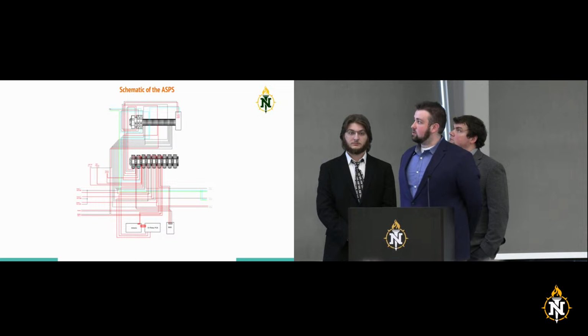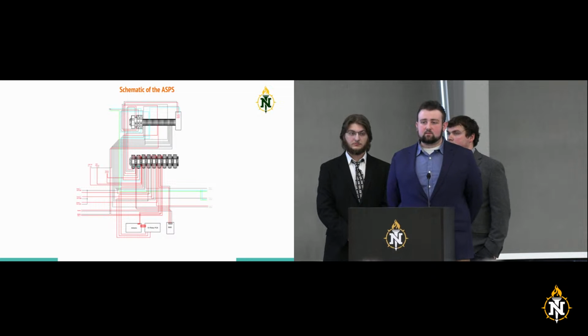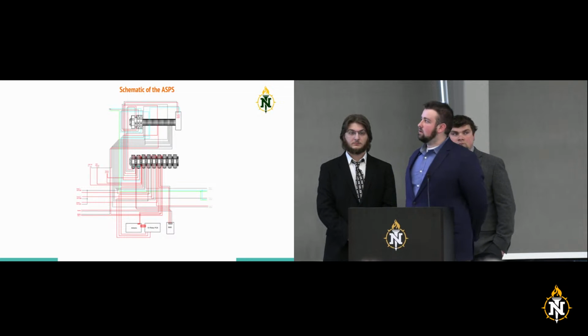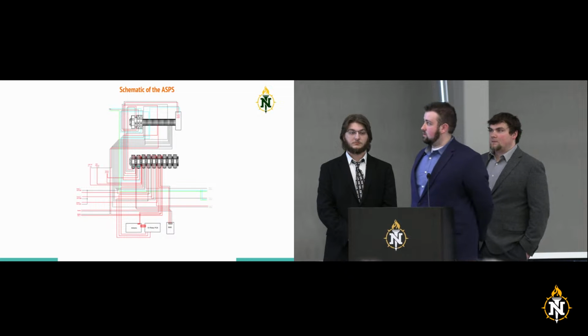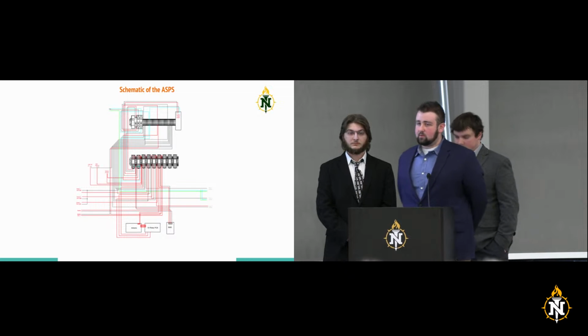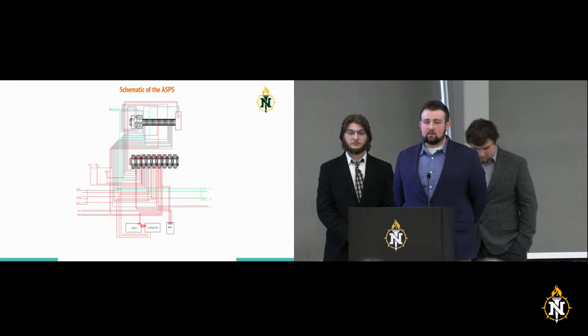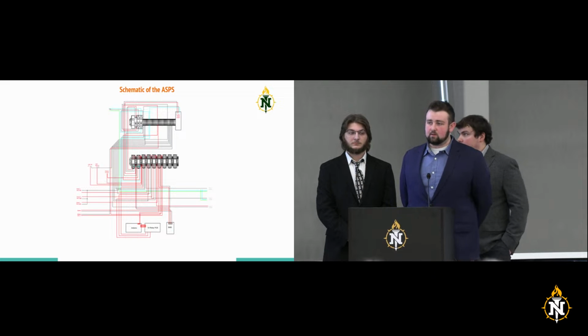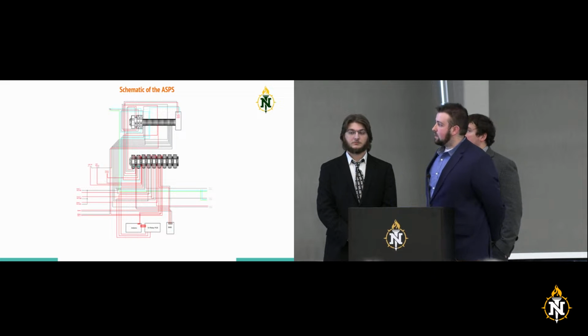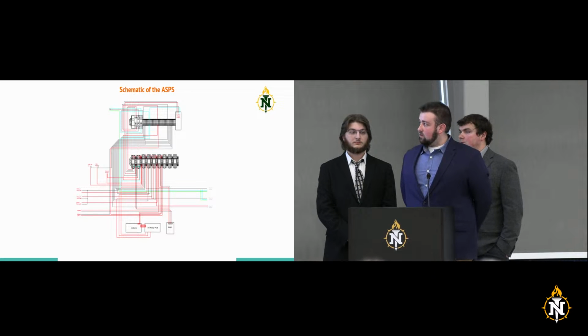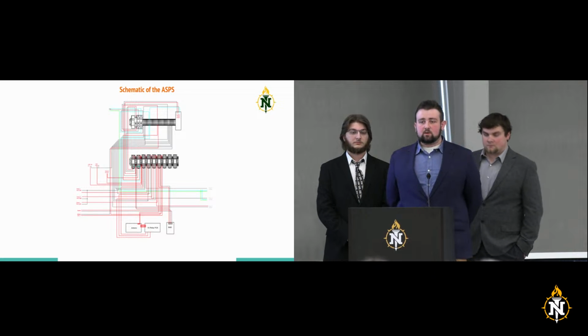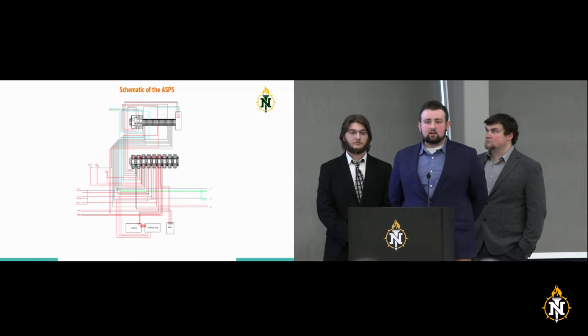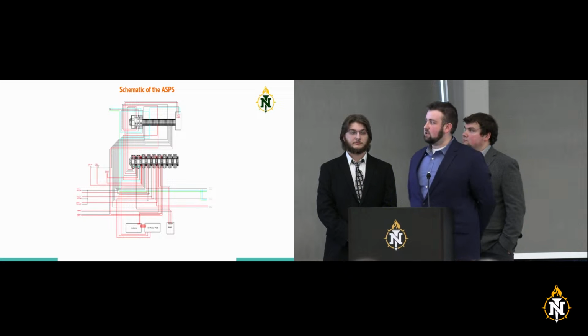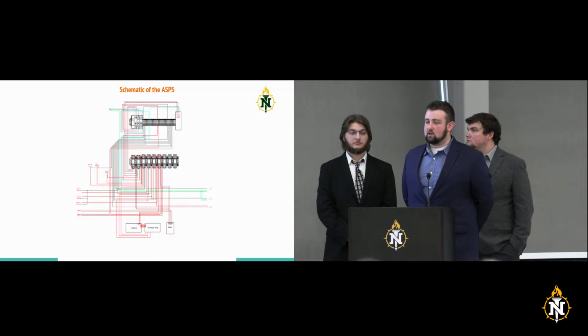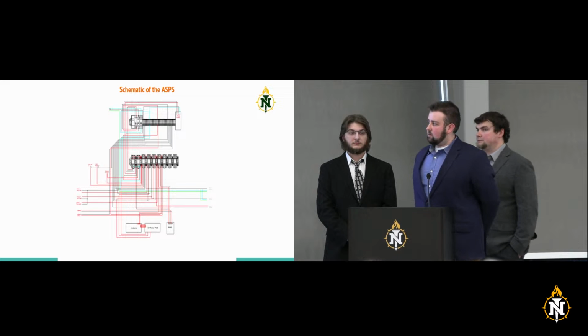We used many terminal blocks that acted kind of like bus bars. On the very end of the rail, you see those two big blocks, which are circuit breakers — one DC type and one AC type on the top. On the second rail, that's our relay rail with electromechanical relays, which Jim will talk about in upcoming slides, but those were basically in charge of turning on pumps and lights in our enclosure.